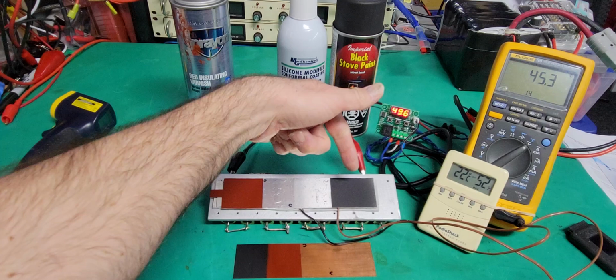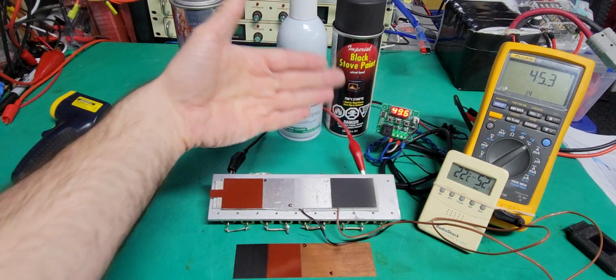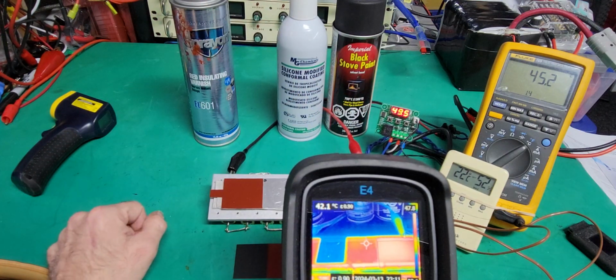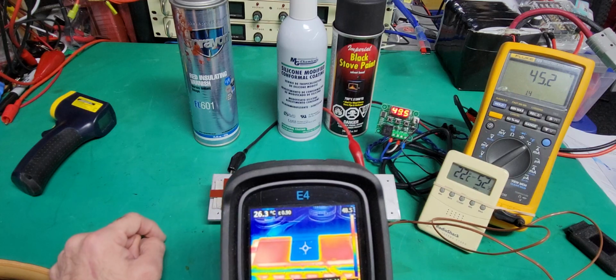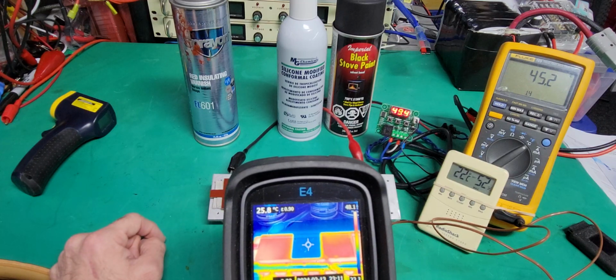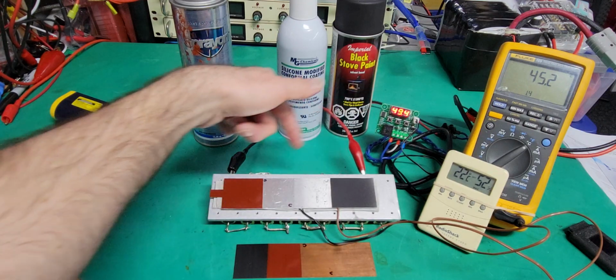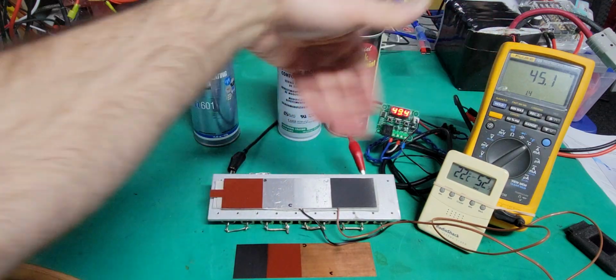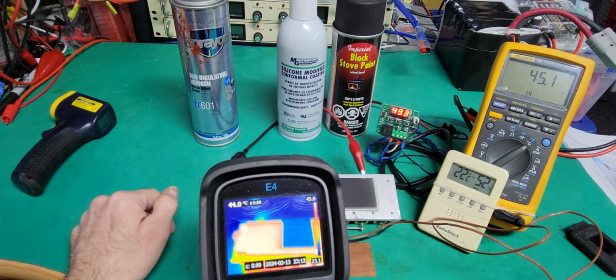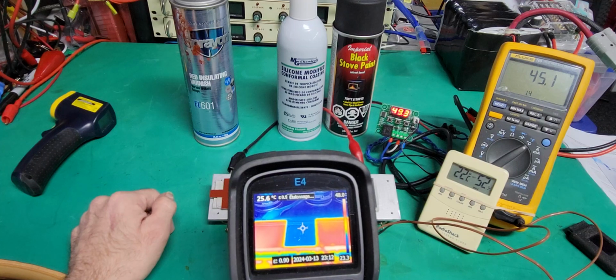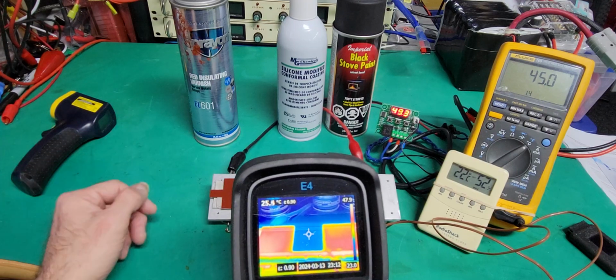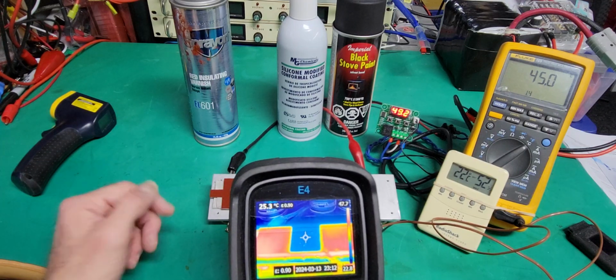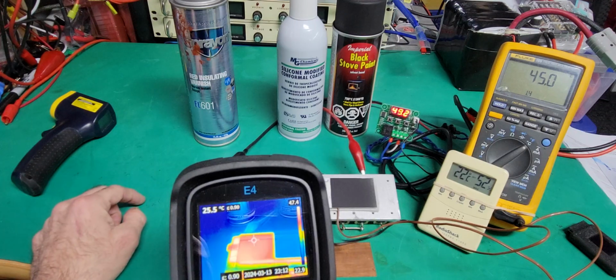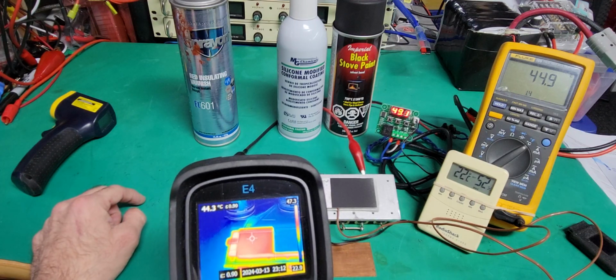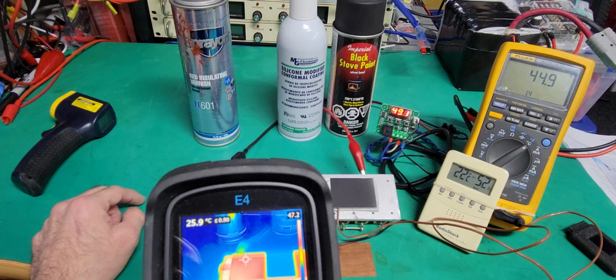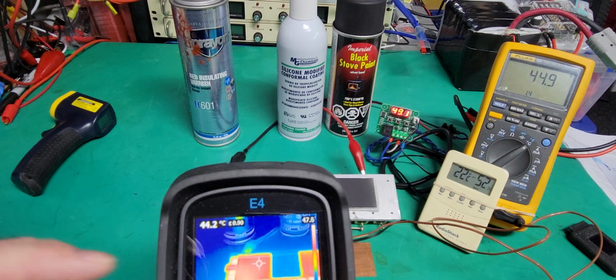You see, these two paints actually give different temperature readings. But now check this out. Check this one. It's 26 degrees Celsius, and it's the same temperature. It's about 45 degrees Celsius in reality. It's not 26 like you see here. So people that don't pay attention to that will get false readings. And the next one here is 44 degrees Celsius. You see 44 with the little target here.